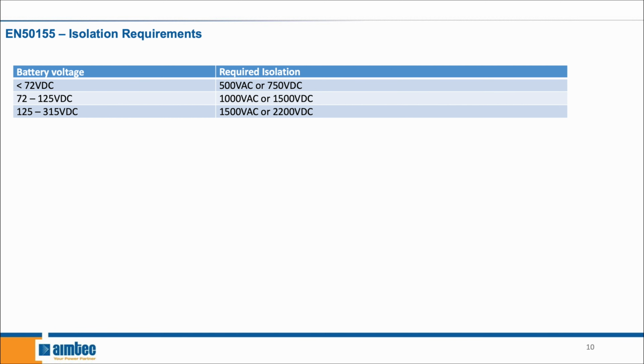Next, moving on to the isolation requirements. The standard specifies the minimum isolation and insulation requirements. The minimum insulation value is 20 megaohms under the 500 VDC test. The isolation requirements are shown in the table: below 72 volts, the required isolation is 500 VAC or 750 VDC; between 72 and 125 volts, 1000 VAC or 1500 VDC, and so on. The test voltage should be maintained for 1 minute for a type test and 10 seconds for a routine test.